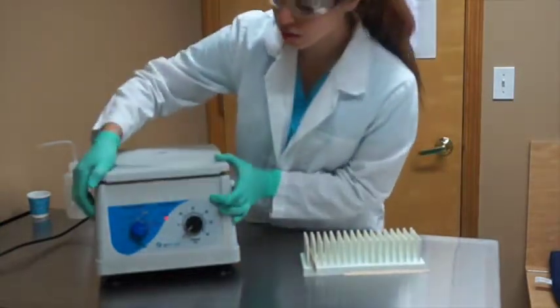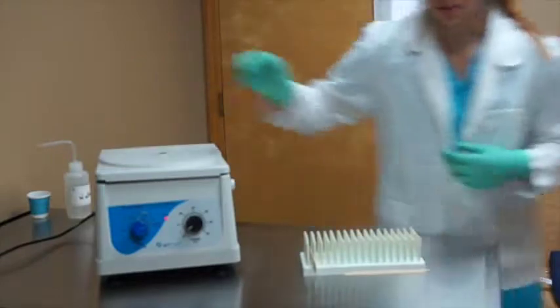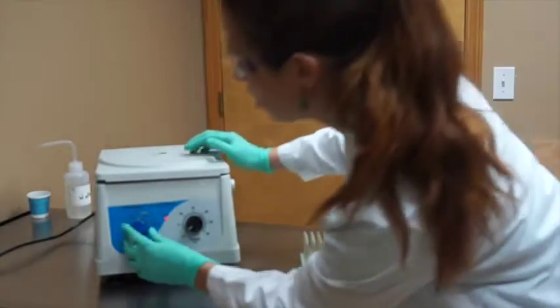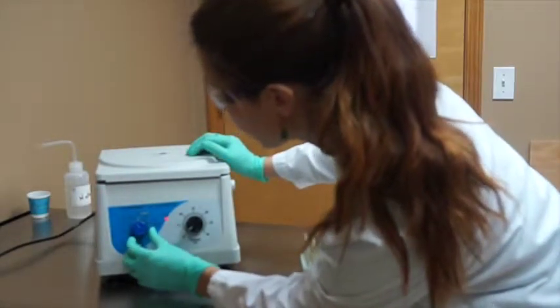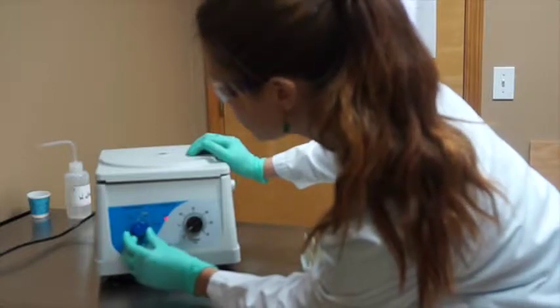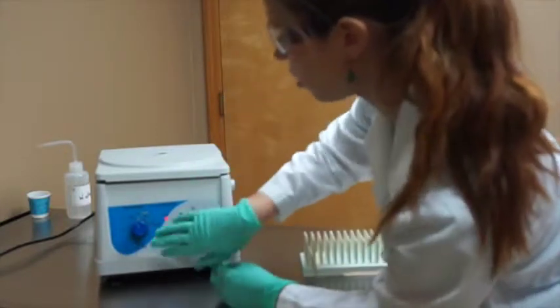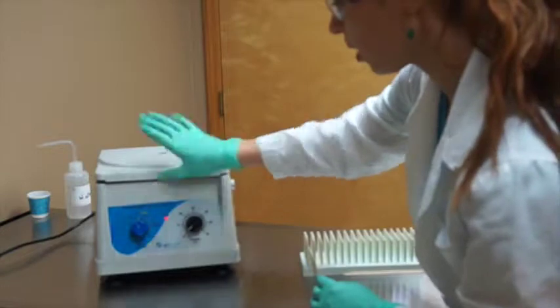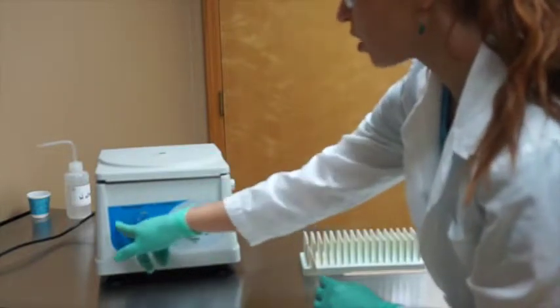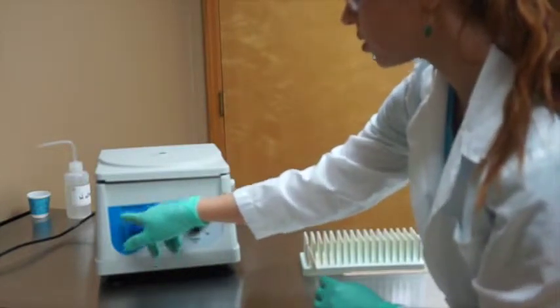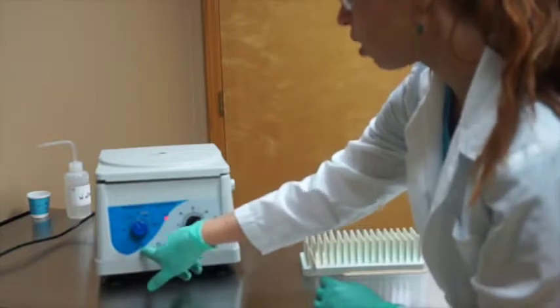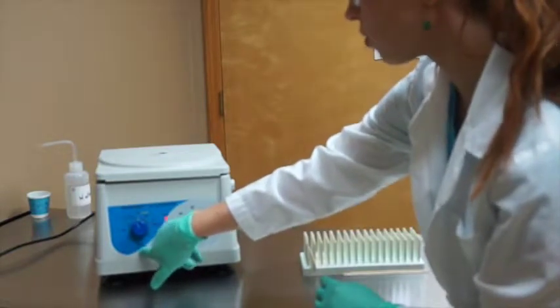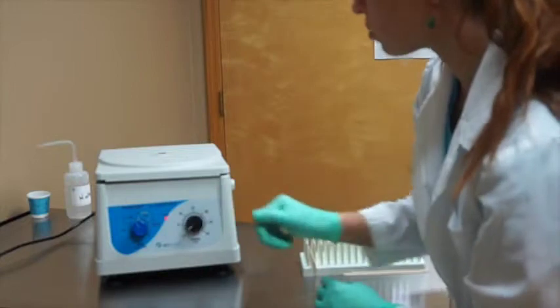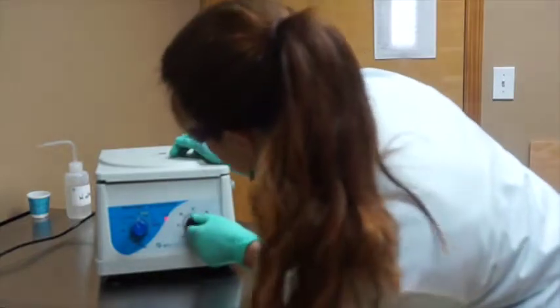We're going to shut our centrifuge. I'm going to come around here and then we're going to set it on about 1300 to 1500 RPM. Our spinner centrifuge has a preset setting for fecals, and it sets it automatically to 1500 RPM. So we'll do that for 3 to 5 minutes.